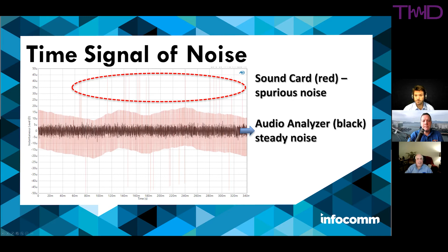So going back to the high order harmonic stuff. This was a 0 dBFS signal that I put into both devices. Here is the AP, and here's the sound card. Notice the Audio Precision shows a second harmonic, third harmonic, and a few upper level harmonics. But look at more of these higher order harmonics. Again, they are very low in level, but I can tell you from firsthand experience that there are distortion artifacts, and on the speaker side, audible rub and buzz, where those high order harmonics can be minus 110, minus 120. So if your measurement device has high order harmonic distortion in that minus 110 range, it might give you a false impression that your device has worse high order harmonic distortion than what it is actually putting out.